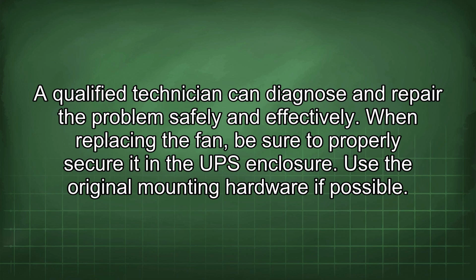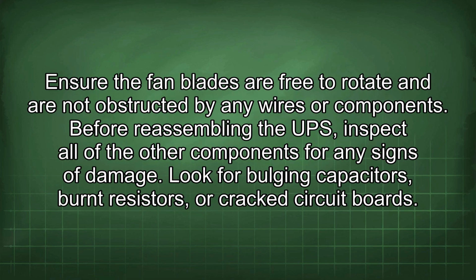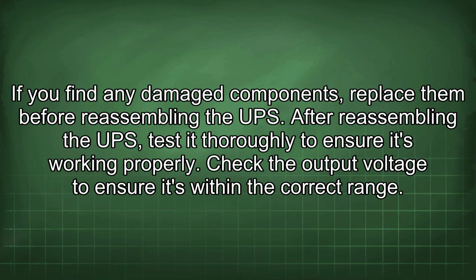When replacing the fan, be sure to properly secure it in the UPS enclosure. Use the original mounting hardware if possible. Ensure the fan blades are free to rotate and are not obstructed by any wires or components. Before reassembling the UPS, inspect all of the other components for any signs of damage. Look for bulging capacitors, burnt resistors, or cracked circuit boards. If you find any damaged components, replace them before reassembling the UPS.